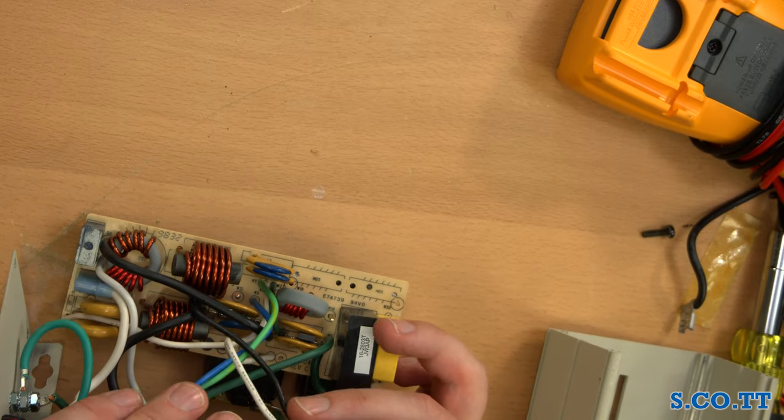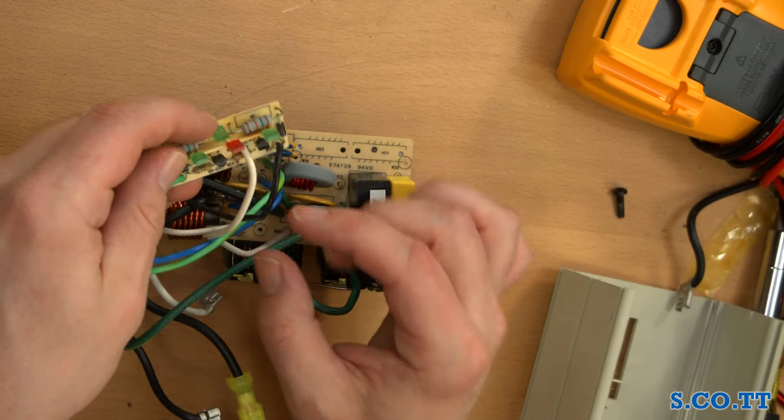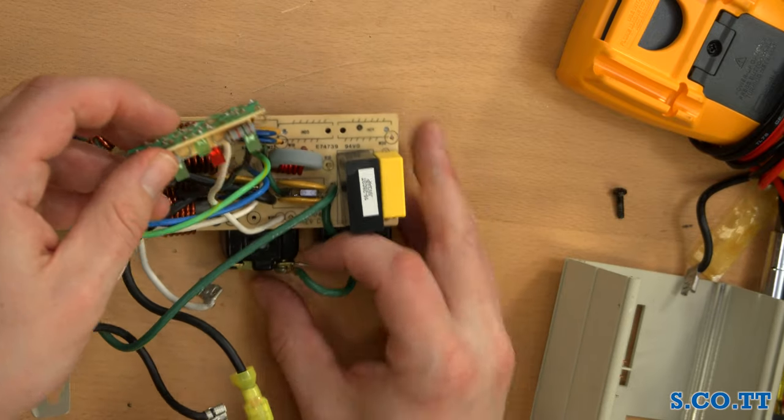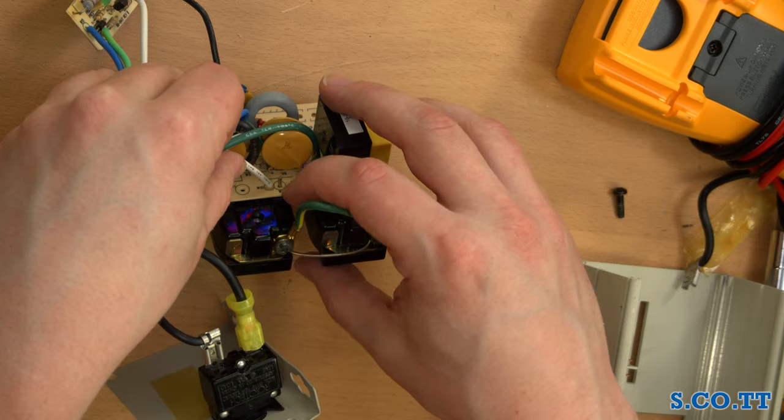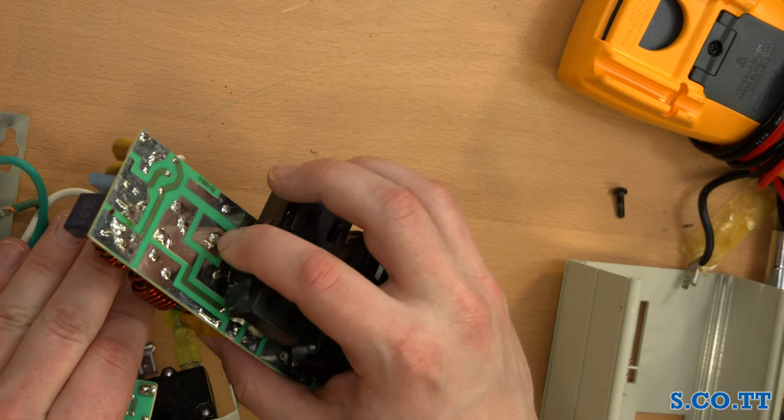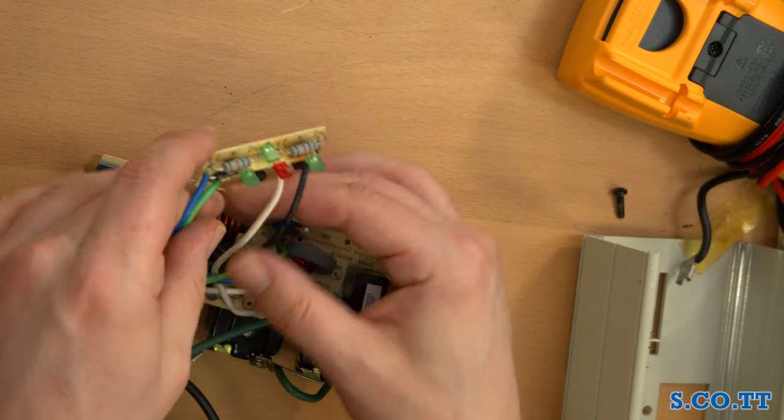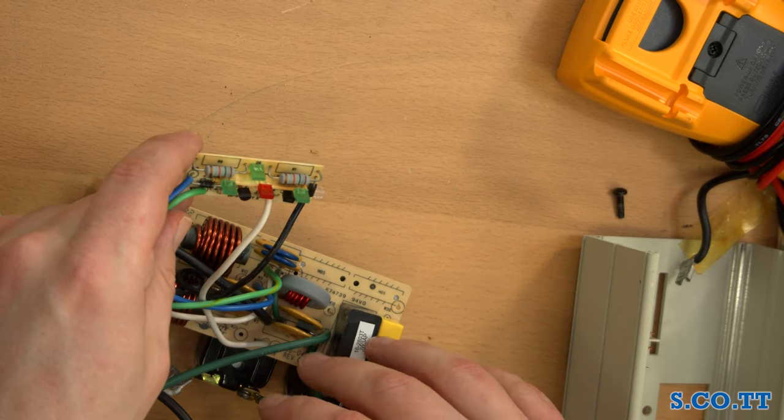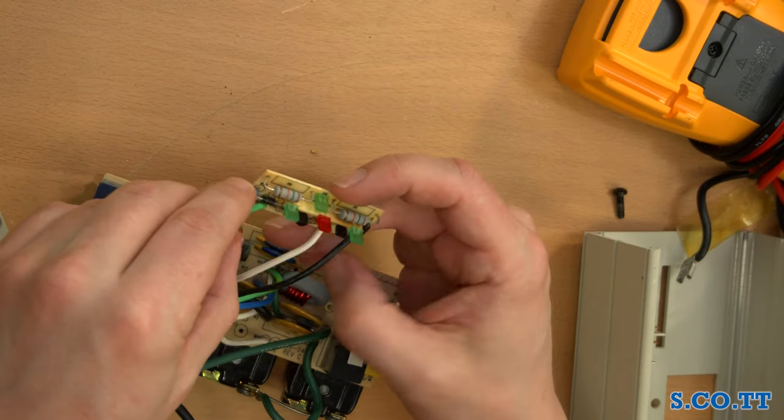Let's see. The resistors aren't warm yet. So, I do believe the black and white wire are just live and neutral, as one would expect. I see no reason why they wouldn't be. In fact, the white wire is definitely tapped into neutral next to the neutral connection on one of these receptacles. And the black wire is tapped on to this pad back here, which is also where the main line voltage comes in from the circuit breaker. So yeah, this is, these two are just powering the board. So whenever the circuit, whenever the devices plugged in, those will have power. Providing the circuit breaker hasn't tripped and the switch is on. And then I'm guessing these two leads are fault indicator leads.